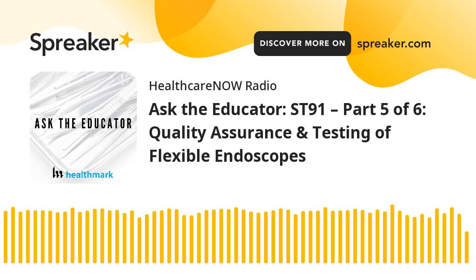Yeah, Kevin, I think that's a great question. I just wanted to start with a reminder of what the requirements are now for cleaning verification in the new ST91. It's a shall, so a requirement of the standard, that all high-risk scopes be monitored with a cleaning verification test every time they're processed. And for non-high-risk scopes, a statistically significant portion of those. And we talk through in ST91 how to figure out what that is. So if you're not doing anything for cleaning verification, you really should be doing something at this point based on what the standards say, and AORN and SGNA have recommendations for it too. So it is time for everybody to get on board with it, especially if you're doing those high-risk endoscopes like duodenoscopes, bronchoscopes, EUS, EBUS, ureteroscopes, cystoscopes. All of them are considered to be high risk.